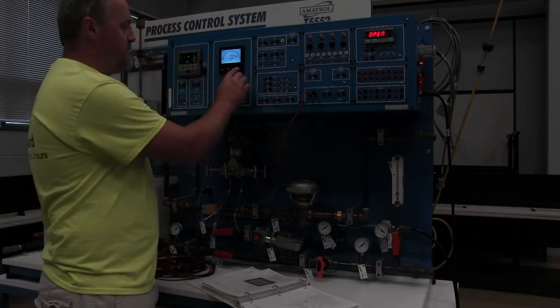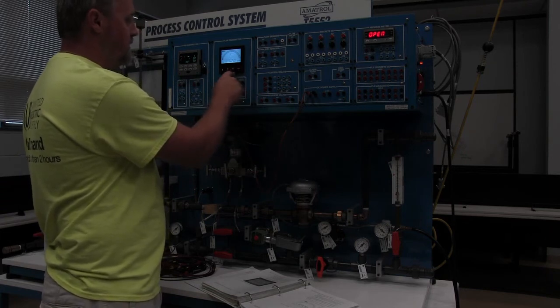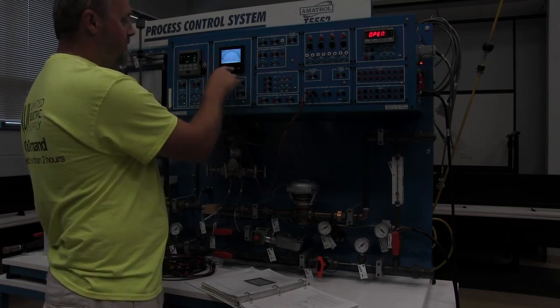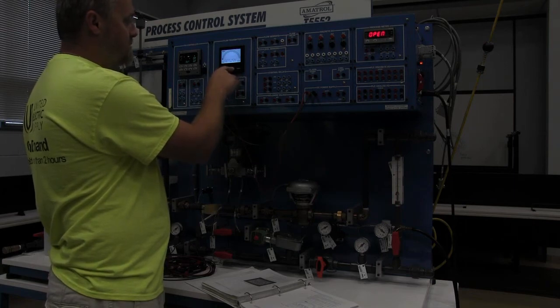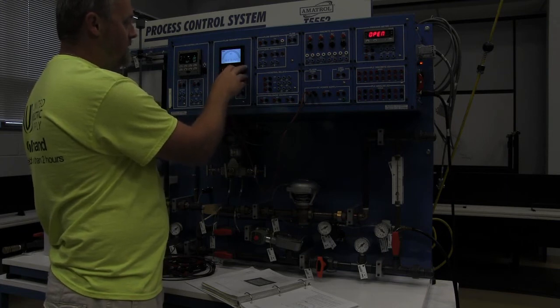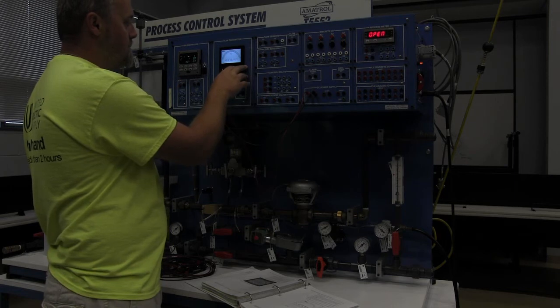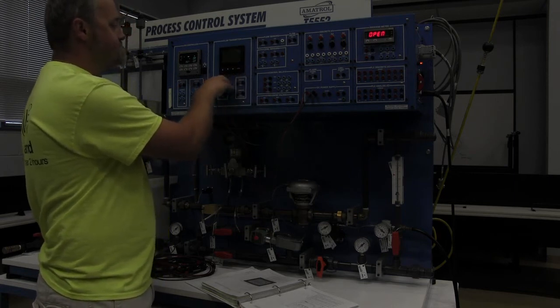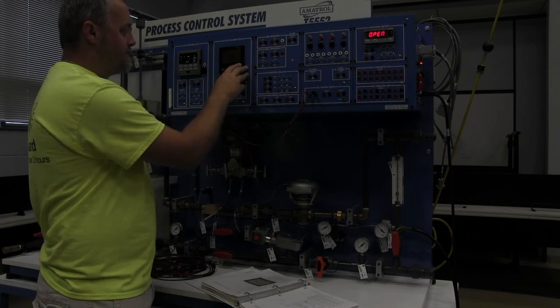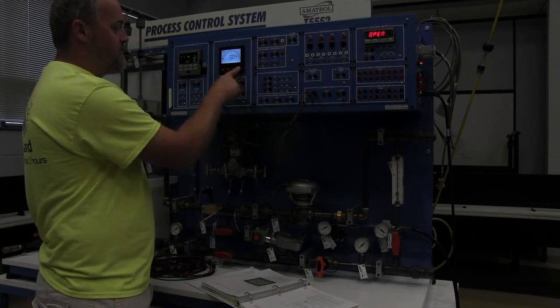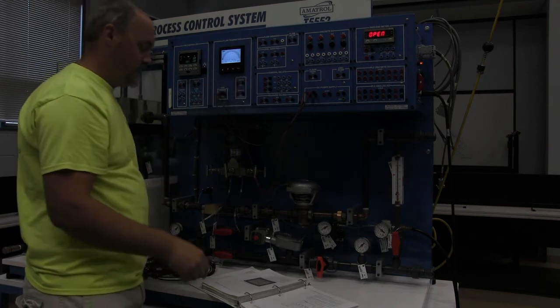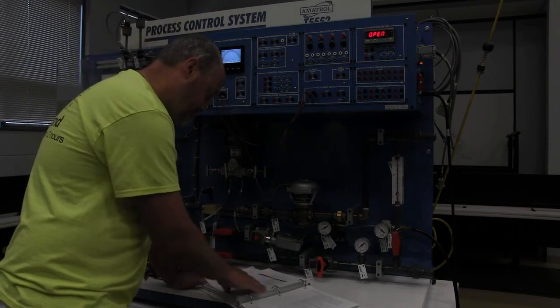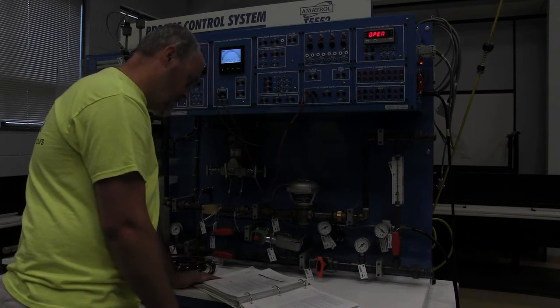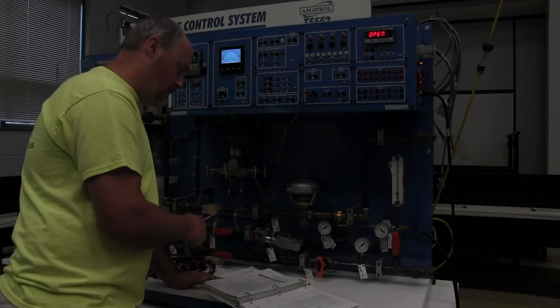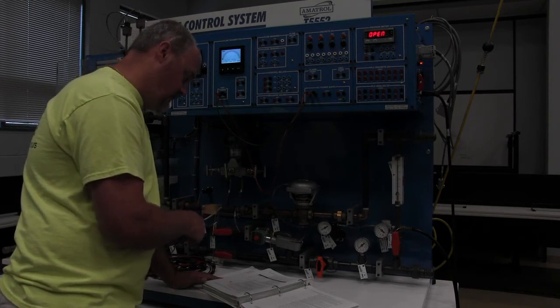But if we want it to go into the menu mode, we press and hold for 3 seconds. Once we go into it, we can calibrate it. Input, loop, relay, or options. It says no hold outputs. So if we want to go in the menu, push and hold for 3 seconds. That's going to take us into the menu. Perform the following sub-steps to calibrate. We're not going to calibrate it, it's already calibrated, so we're not going to go through the calibration of it.